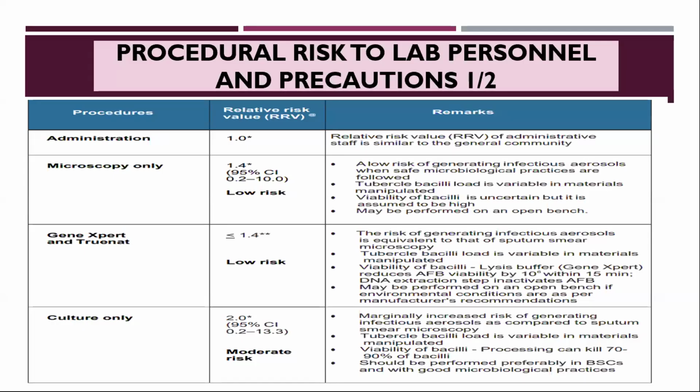If you are doing GeneXpert and TrueNat, this is also low risk. It is the same risk as smear microscopy, equivalent to smear, but depending on the load of bacteria in the sample and the viability of bacilli. In the case of GeneXpert, we add the lysis buffer, so the bacteria become non-infectious within 15 minutes, and the DNA extraction step inactivates the AFB. So this can even be performed on an open bench if environmental conditions are as per requirement. We have already talked about environmental conditions. If we have exhaust and air changes occurring, we can do it in an open area also.